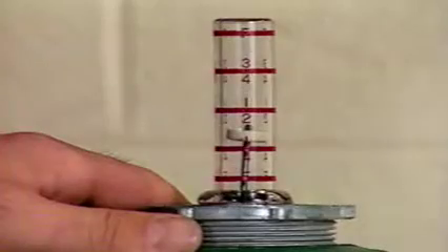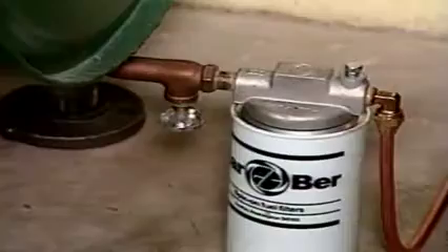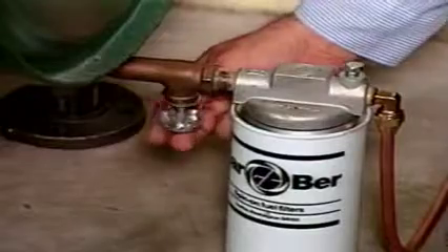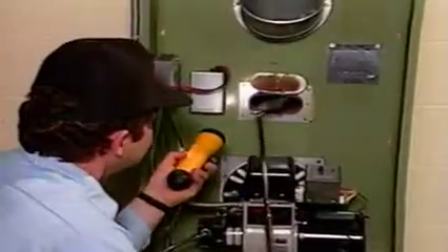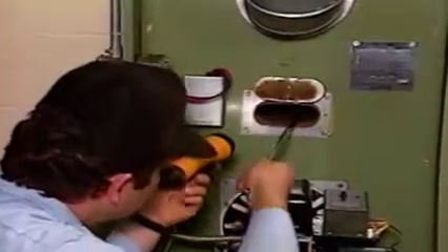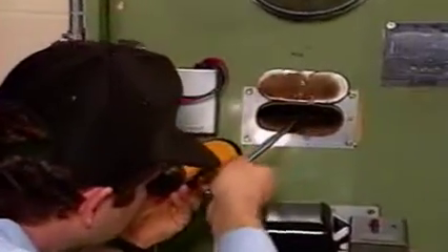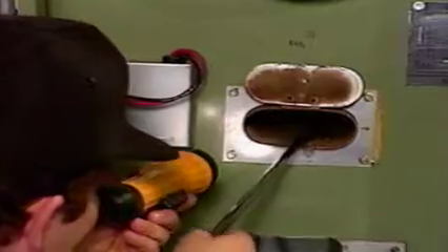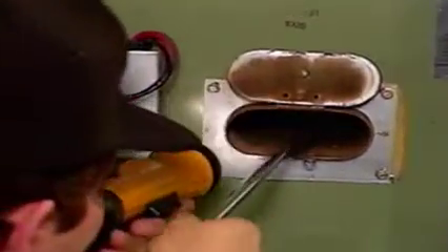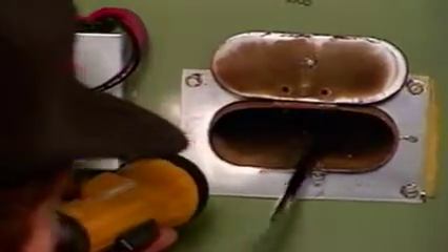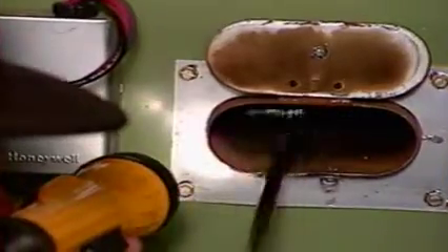Armed with any verbal input from the homeowner, start a systematic check of obvious causes for no heat. Is there oil in the supply tank? Are all the valves in the supply line open? Is the thermostat set to call for heat? After you've checked, look at the burner itself, starting with the combustion chamber. If the homeowner repeatedly pressed the safety reset button, there could be liquid fuel oil accumulated in the combustion chamber.